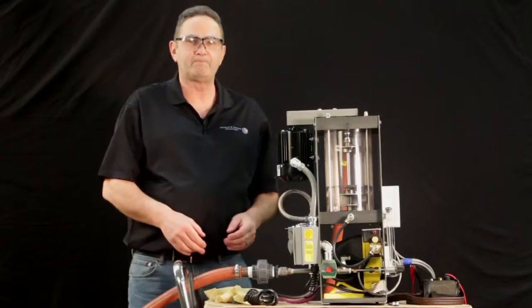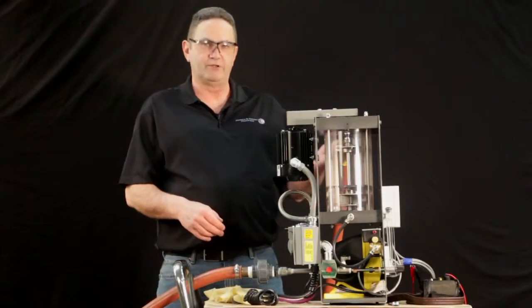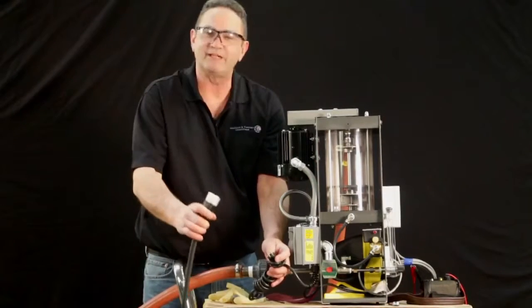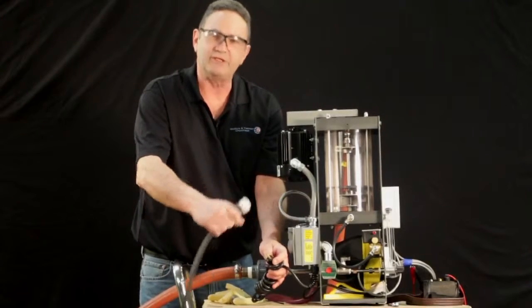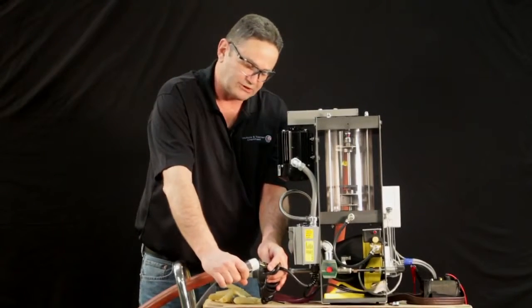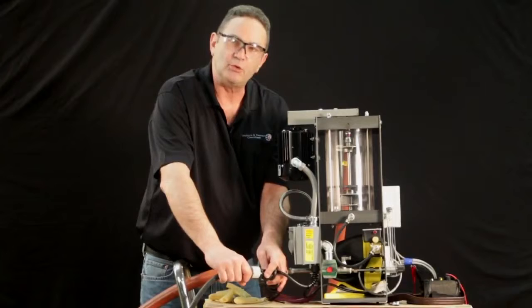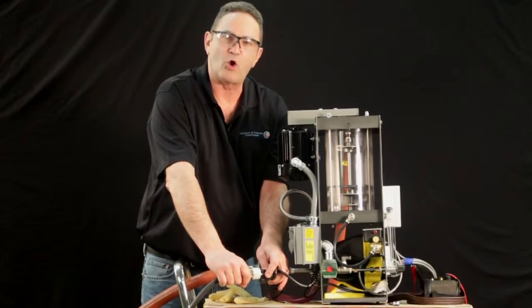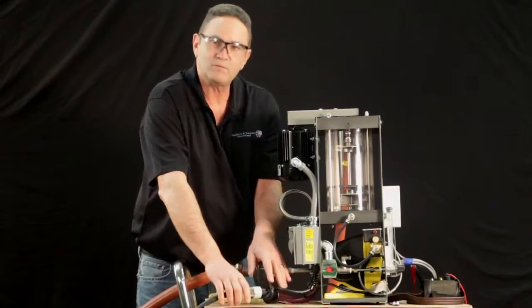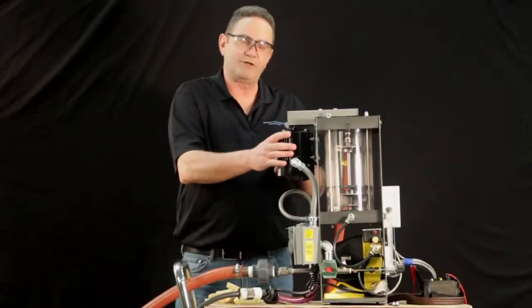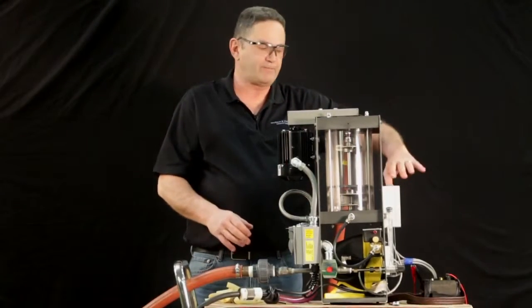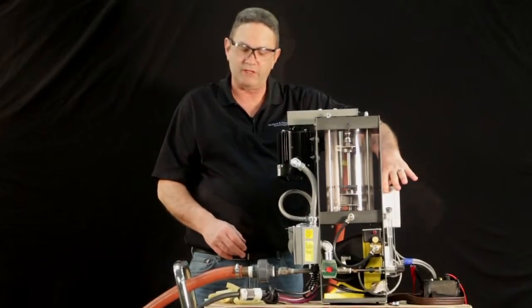Next step, energizing to fill the mix chamber. Ensure that your receptacle is amped properly. The unit is 6 full load amps. Once you energize it, you will hear the distinct sound of the solenoid opening. You will have no power to your mixer. You'll have no power to your pump. You'll have no power to your REM controller.